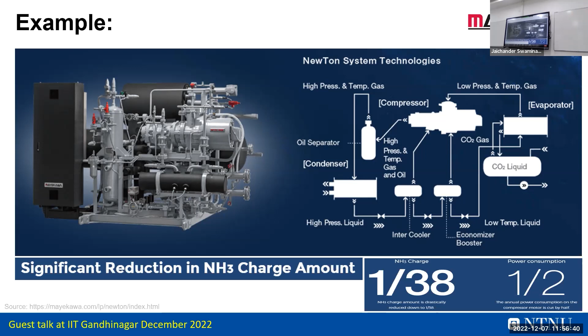Another way is to introduce a low temperature compressor as the first stage of a cascade system. You can even utilize the CO2 at the lower level, I'll show that later. But again, we have a second stage system which may already exist, and we just put the CO2 system at the bottom.